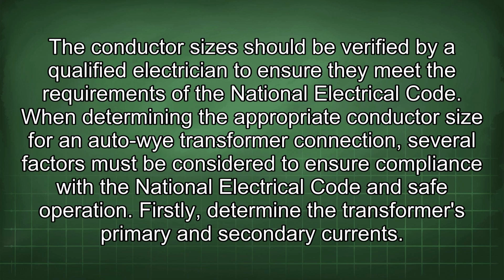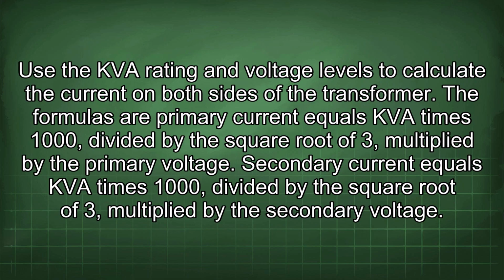The conductor sizes should be verified by a qualified electrician to ensure they meet the requirements of the National Electrical Code. When determining the appropriate conductor size for an Auto-Wye transformer connection, several factors must be considered to ensure compliance with the National Electrical Code and safe operation. Firstly, determine the transformer's primary and secondary currents. Use the kVA rating and voltage levels to calculate the current on both sides of the transformer.